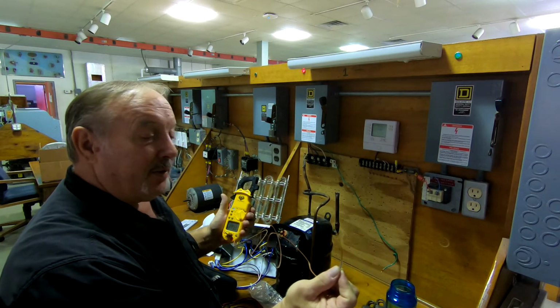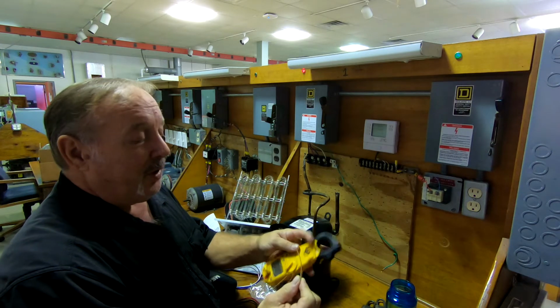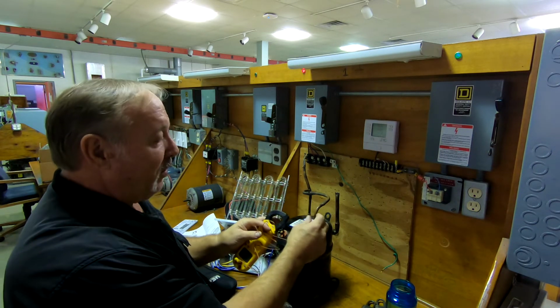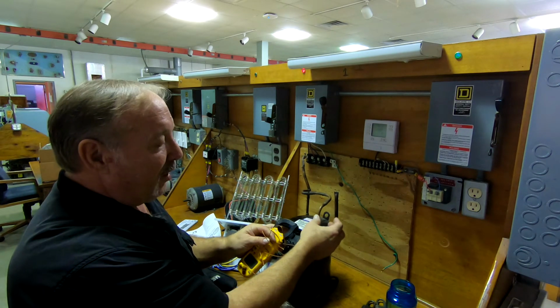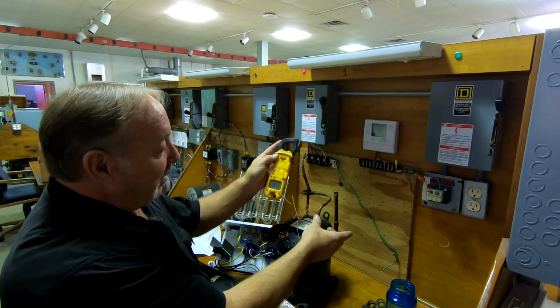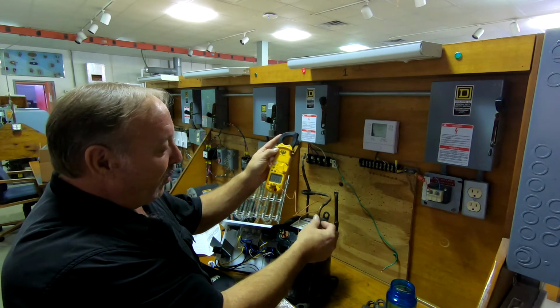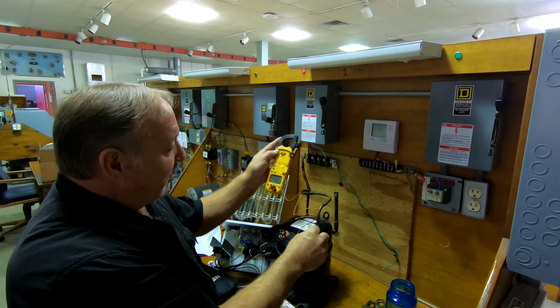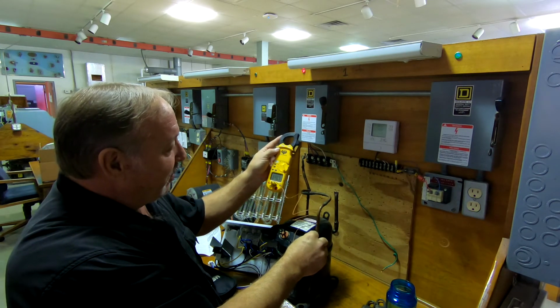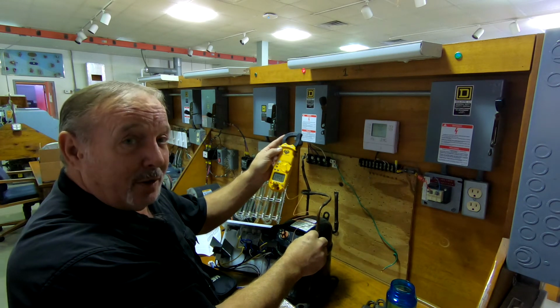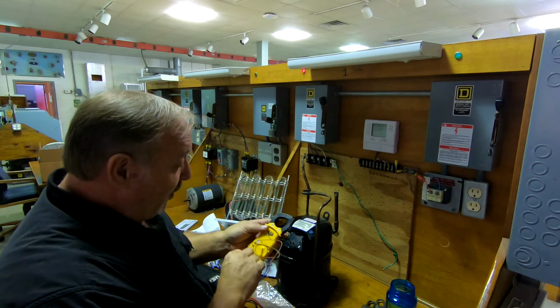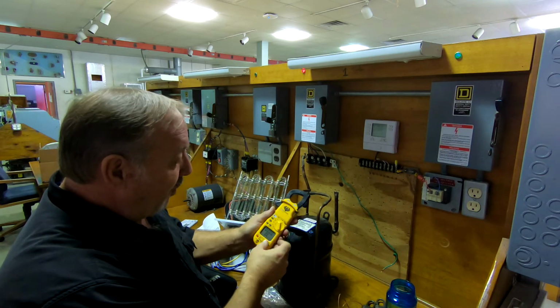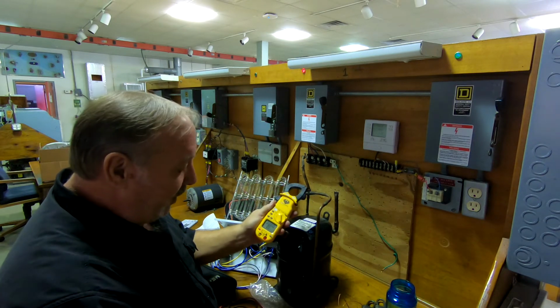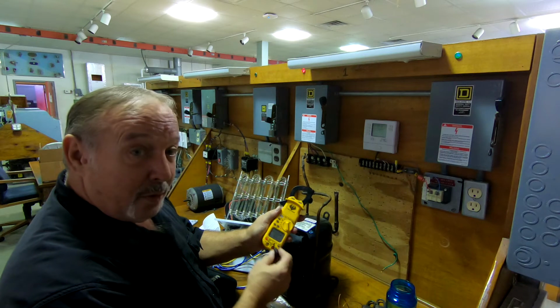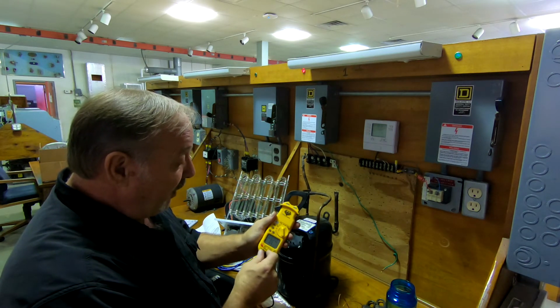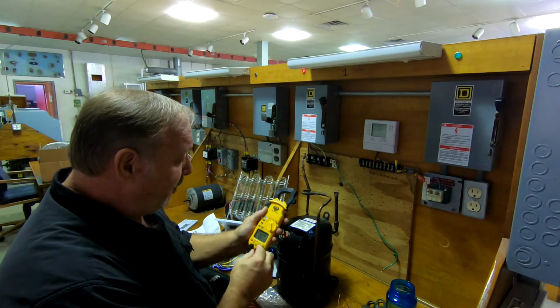The important thing to note is when you're using this probe, make sure that your fingers do not come in contact with it. So in other words, if I was trying to measure the temperature of a discharge pipe, I wouldn't want to put my big fat thumb on it, because now it's 83.5 versus 76, 75. So you can see that you can influence your own readings. So now you remove that, put the switch back in the up position, because in the down position it will not enable you to install your probes. That's a safety feature. So now we'll put the probes back in.